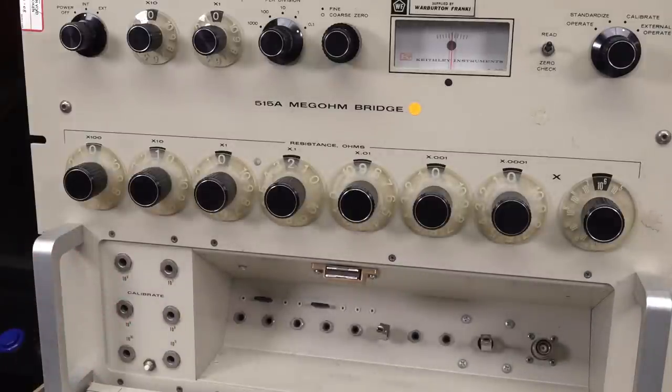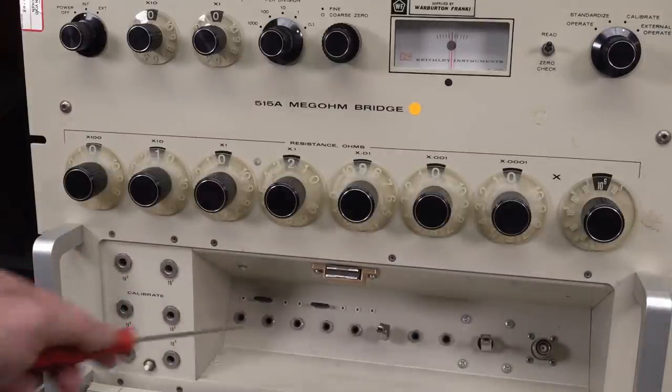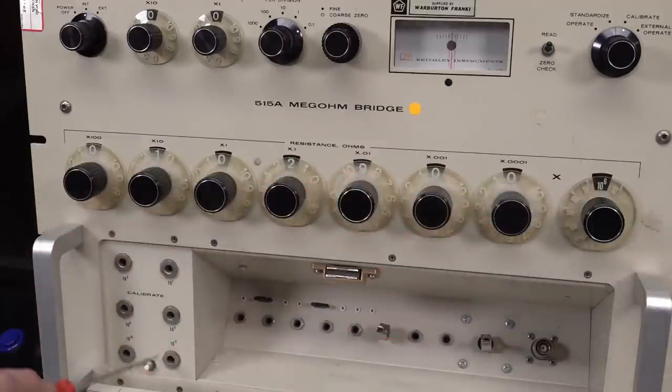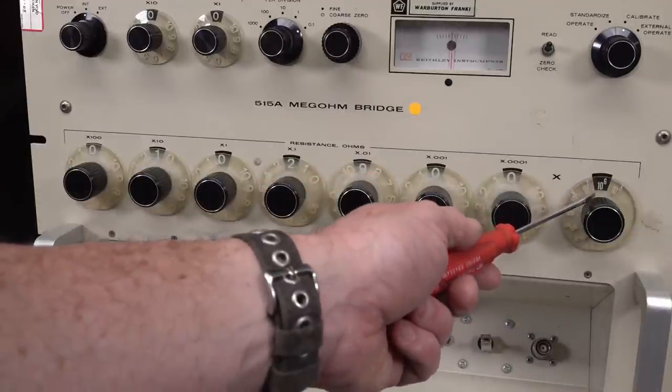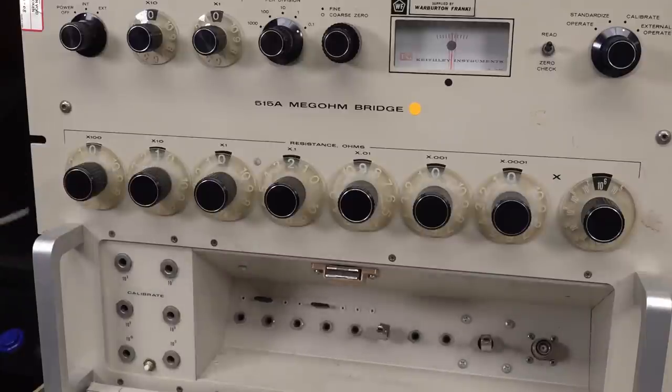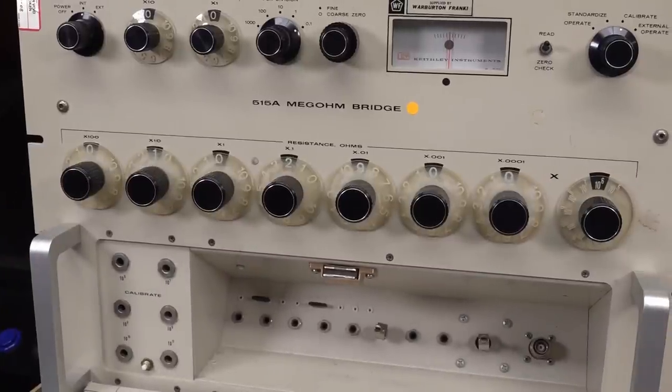Oh, that's going to have to be good enough for Australia. Now, ordinarily, we'd have to go through and calibrate all the different ranges here going all the way up. But we're only going to measure on the megohm range that we just calibrated. So, yeah. I'm just not going to go through and bother to do the rest. Next.